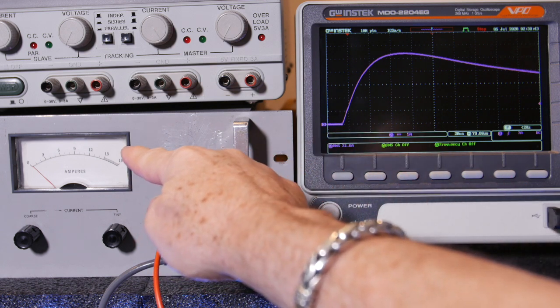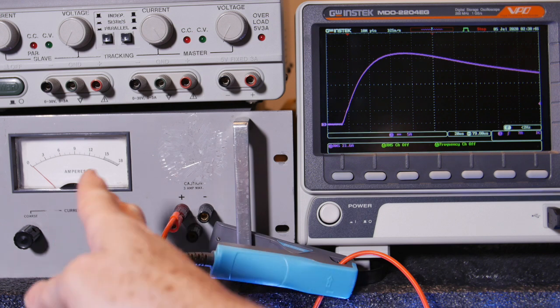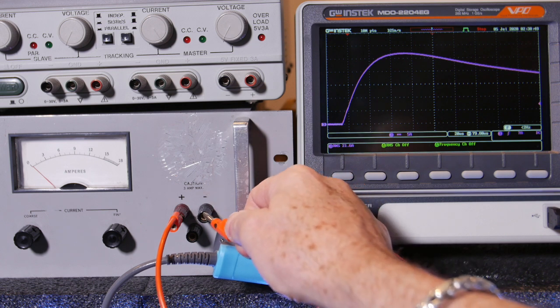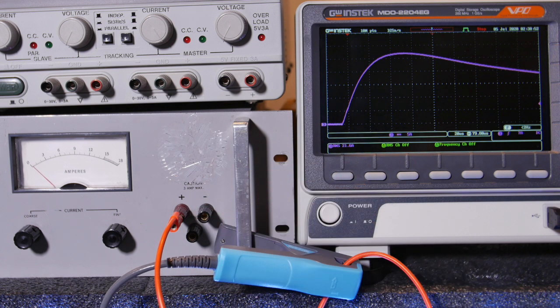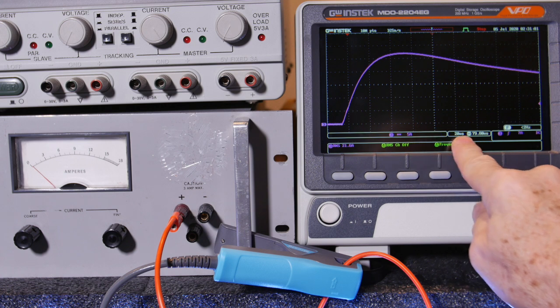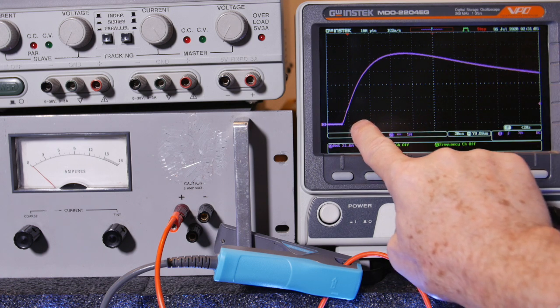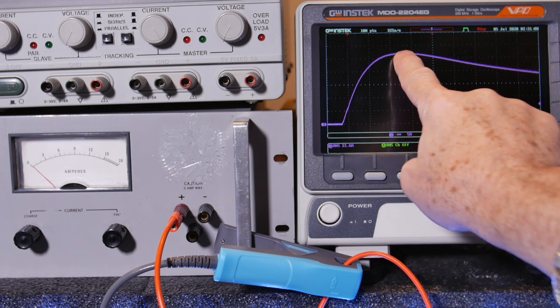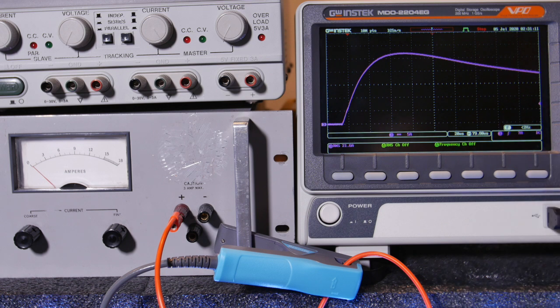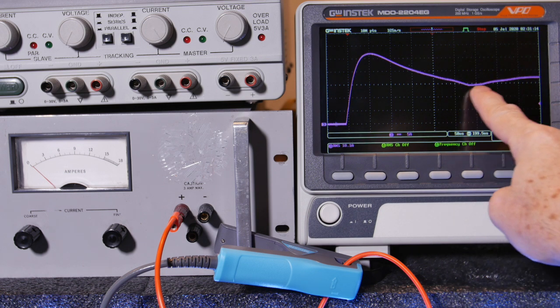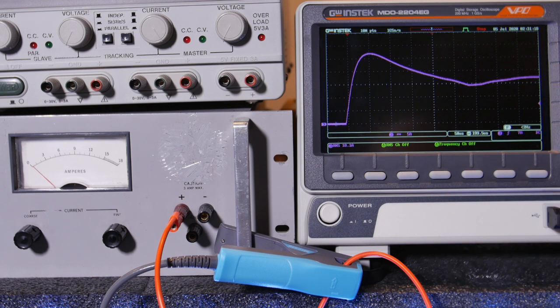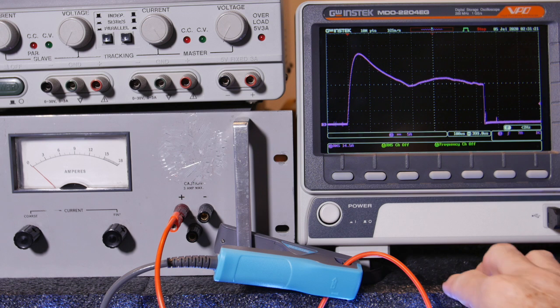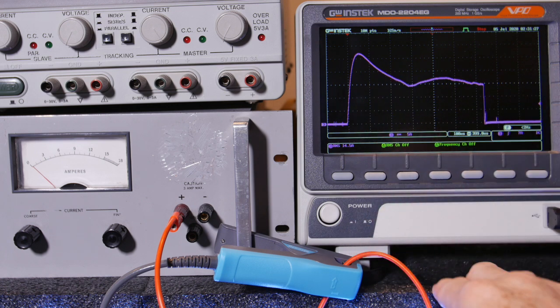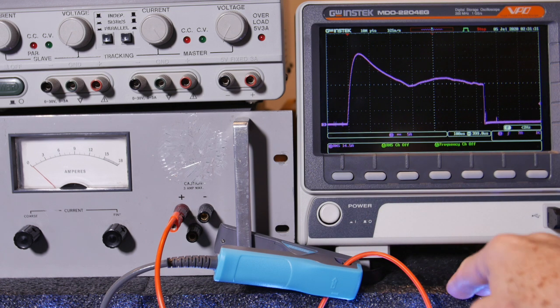And this thing was set for continuous current around 15 to, let's see, I wasn't watching, let's see what it did. Okay, 16, 17 amps, 5, 10, 15, so it looks like it's coming there. I'm going to change the time base from 20 microseconds. So by the way, that was 20 microseconds, so 20, 40, it took about 40 microseconds to peak out. So let's do that. Wow, look at that. I wonder if that's real. Sometimes you don't know if you catch it. Yeah, look at that. I wonder if I caught all that stuff. So this memory is pretty deep. Even though my screen was only set for this, it does catch stuff that you didn't see on your screen. So this could be true.